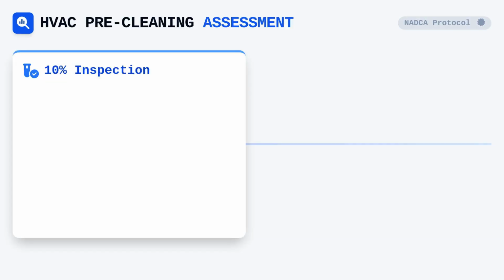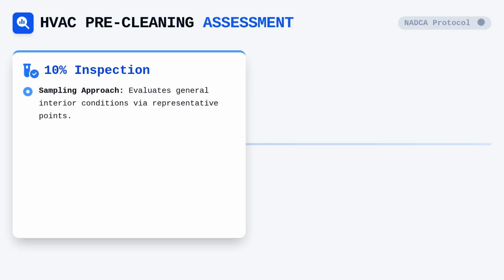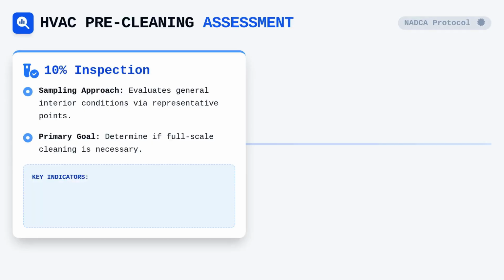The foundation of any successful HVAC cleaning project lies in the accuracy of the pre-cleaning assessment, which is governed by strict NADCA protocols. When we talk about inspection depth, professional standards distinguish between a 10% inspection and a 100% inspection. A 10% inspection is essentially a sampling of the system's interior to assess the general condition and determine if full-scale cleaning is even necessary. During this process, you are looking for evidence of debris, microbial growth, or mechanical failure at representative points within the ductwork.